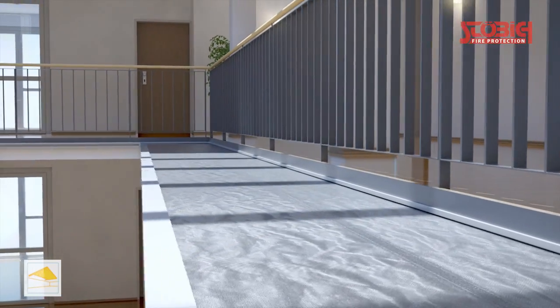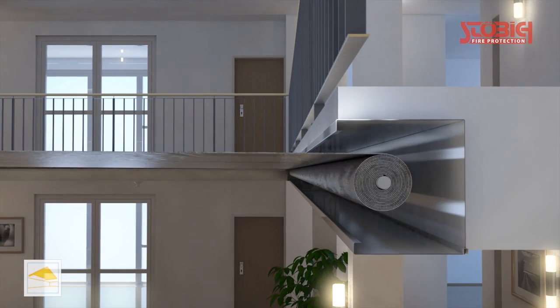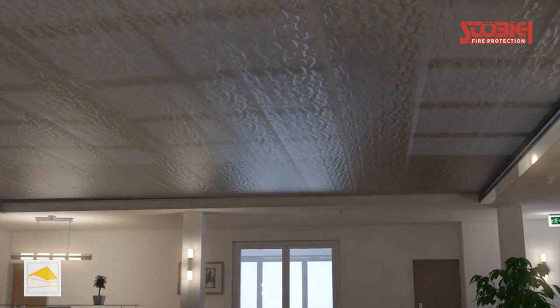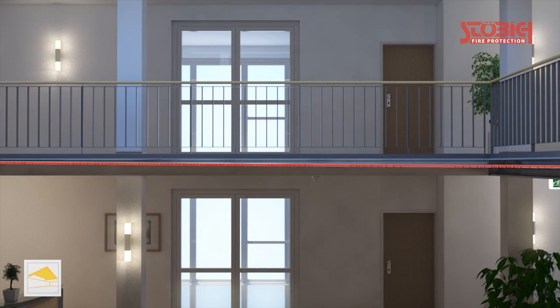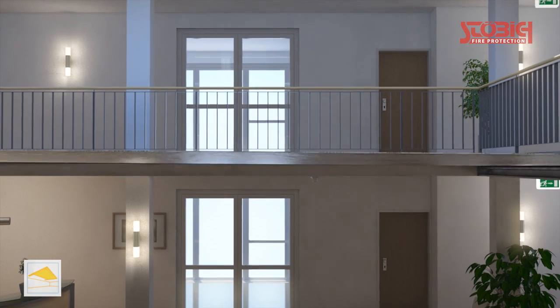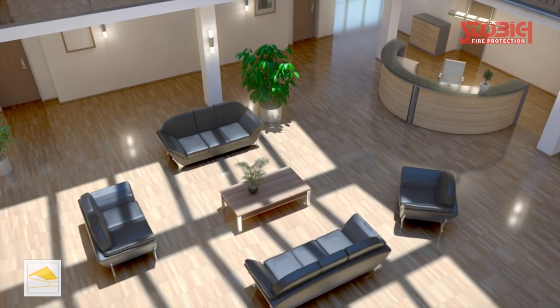The casing opens in case of an alarm and closes the ceiling opening. The fact that large openings can be covered without necessary supporting cables is a novelty. These cables previously avoided a sag of the fabric surface downwards, or a bulge upwards in the case of fire, and are now superfluous due to special struts integrated in the fabric. The FibreShield HC reaches fire resistances E120 — integrity over 2 hours — as well as EW60 — integrity with reduced heat transmission over 60 minutes — classified according to EN 13501 Part 2.